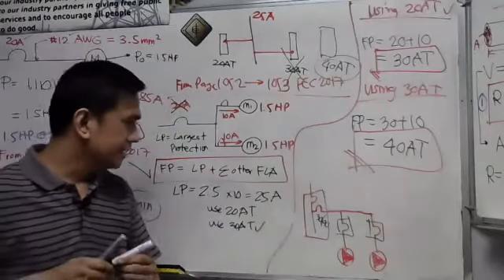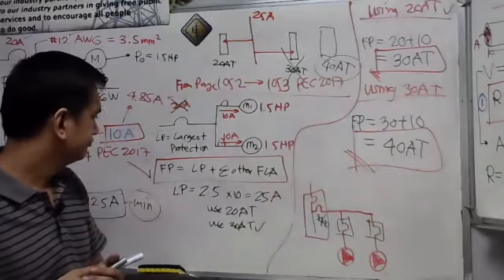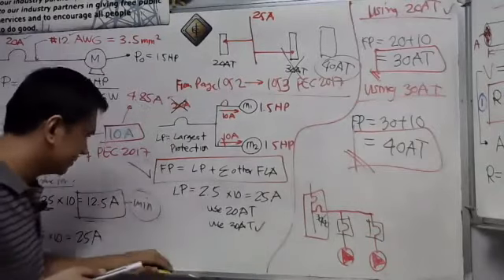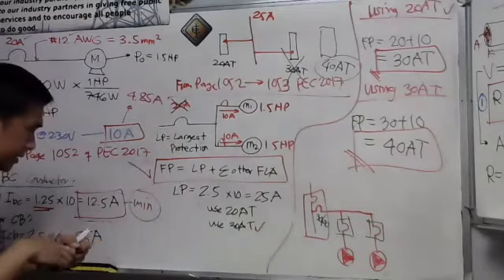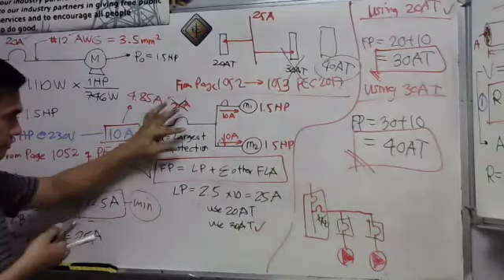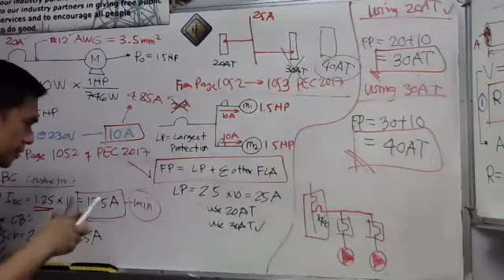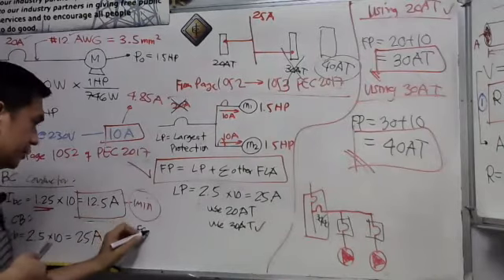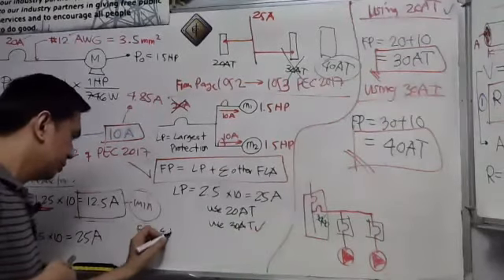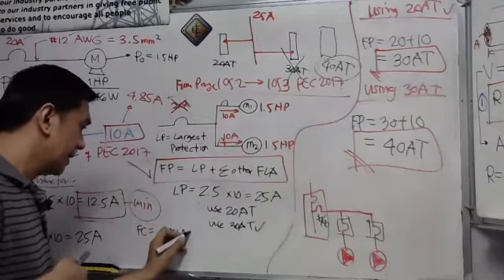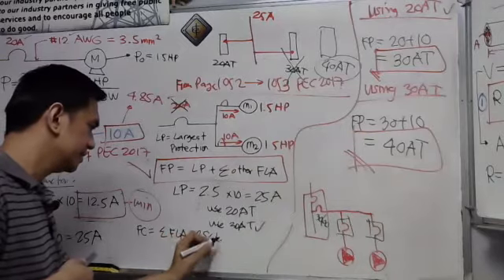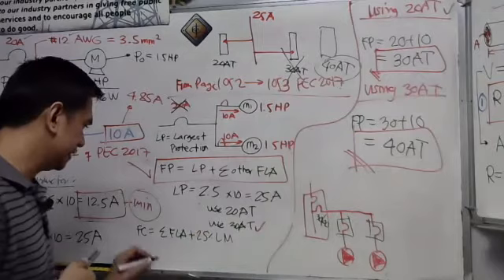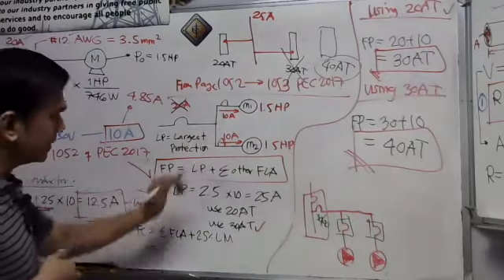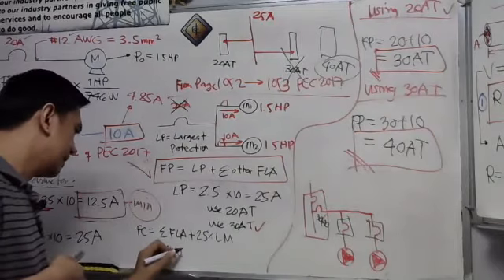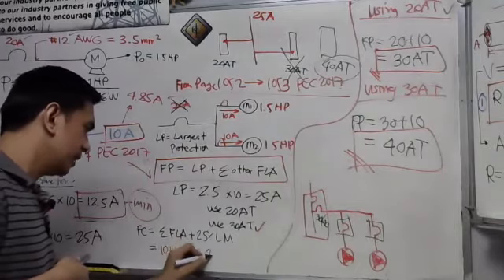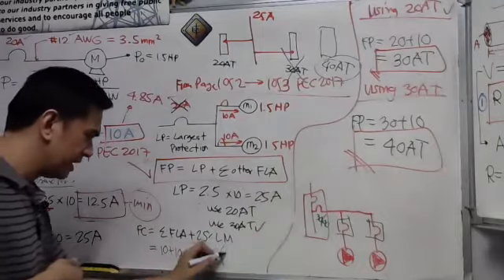Okay? So for this question, I want to add something so that you will learn something today. What about, sir, the feeder wire or the feeder conductor? Let's go over here. The feeder conductor is equal to the summation of the full load amperes plus 25% of the largest motor. Largest motor. How is this, sir? Let's have the full load ampere. 20 plus 20, 10 plus 10. So we have 10 plus 10 plus 25%, 0.25. Okay, largest motor. Just put here 10 because they're just the same.